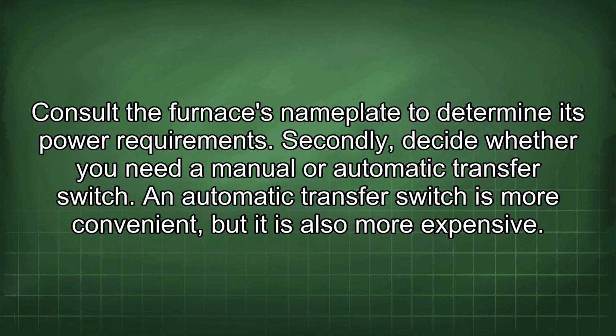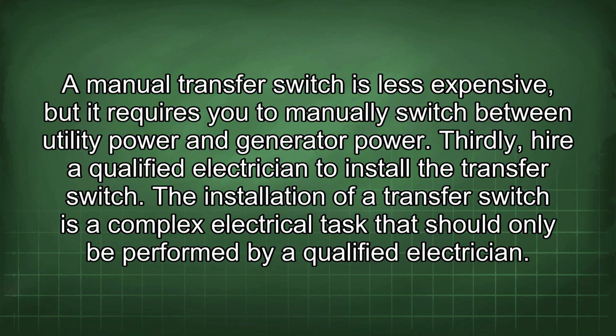Secondly, decide whether you need a manual or automatic transfer switch. An automatic transfer switch is more convenient, but it is also more expensive. A manual transfer switch is less expensive, but it requires you to manually switch between utility power and generator power.